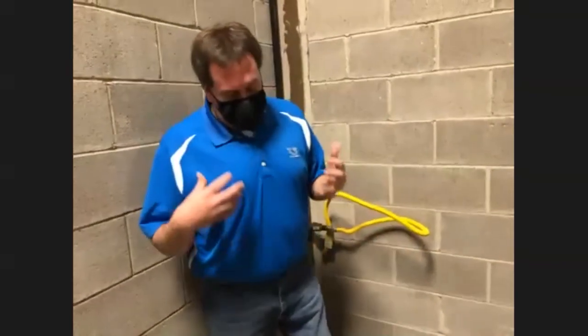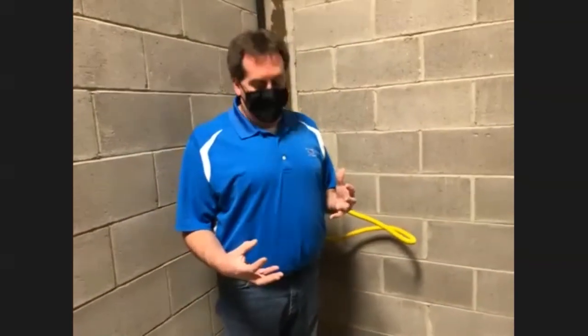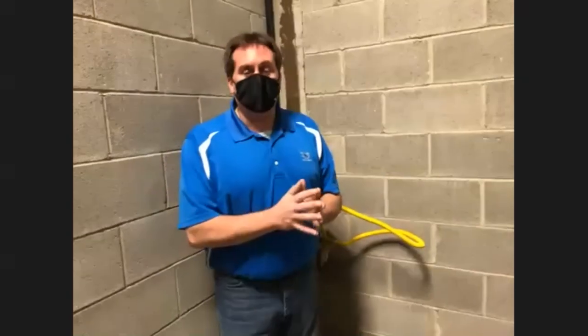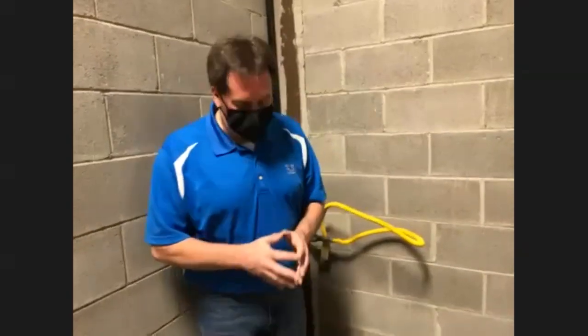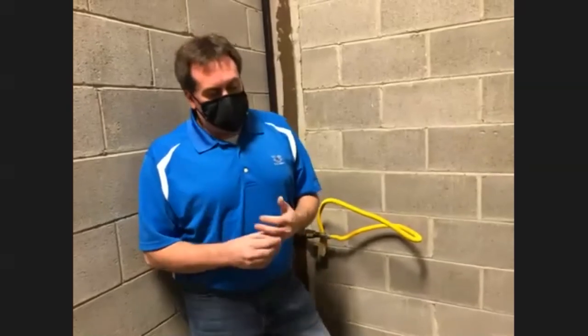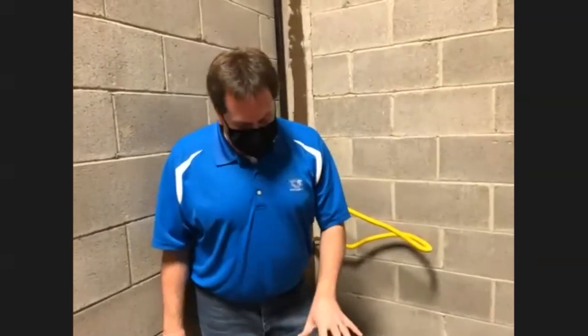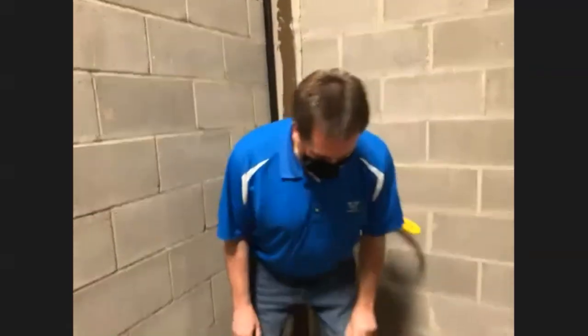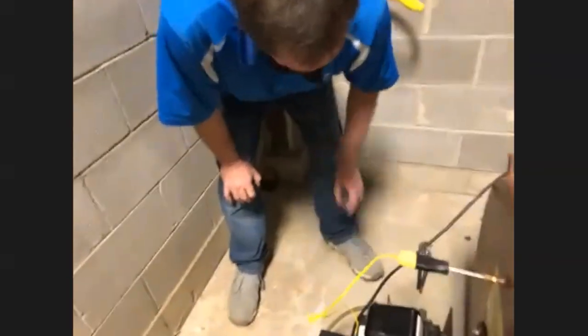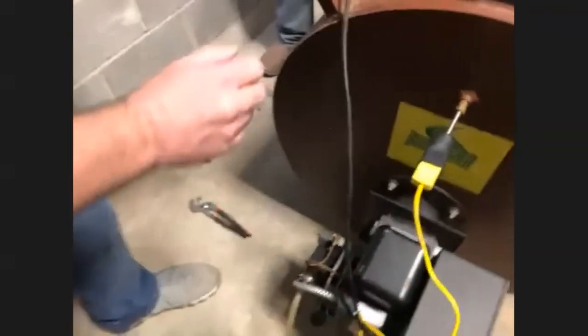If you're going into any troubleshooting on these, again, there's not a lot to them. They're very robust units. Most times you're either not going to have the fuel supply. And if that is the case, you want to verify everything is operating with your fuel line. So as you go through, one of the first things you want to check is the fuel supply. When this is trying to operate, you may need to come around that side, I believe.